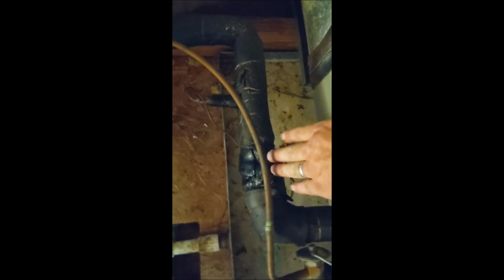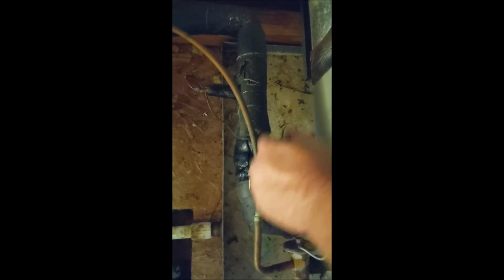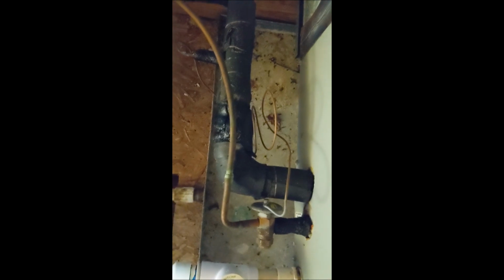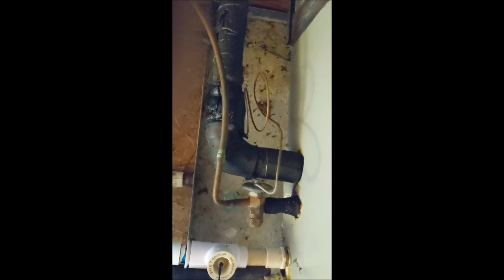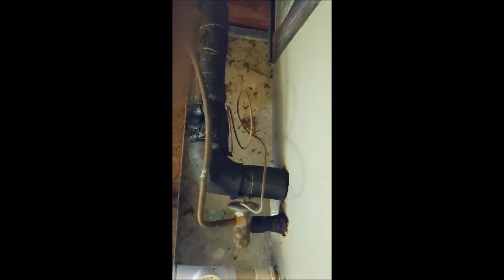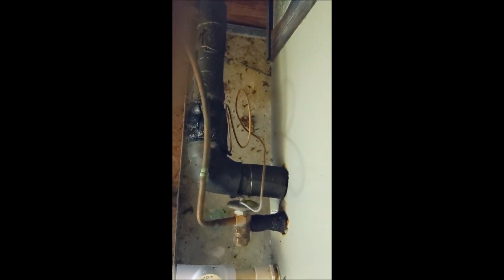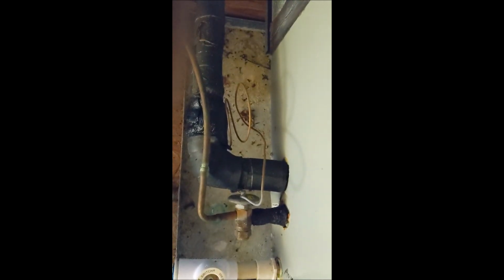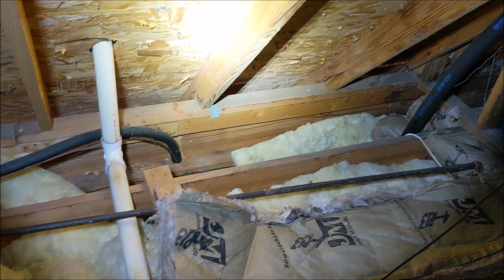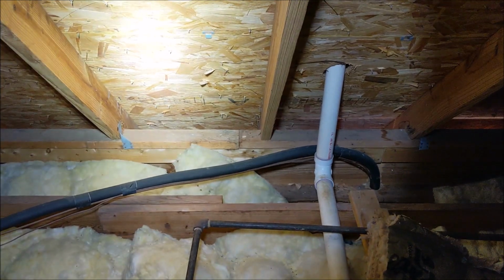This is an expansion valve here, right here. And this is a thermocouple and it's hooked up to the suction line. This is the liquid line and this is the suction line. And basically what this does is it senses the temperature, superheat, subcool, and it tells the refrigerant to open up when there's a heavy heat load and then to shut down. It does the same thing as an orifice that kind of gives it a mist across the evaporator coil. It's supposed to be better. Down on the lower section we do have some hurricane clips.